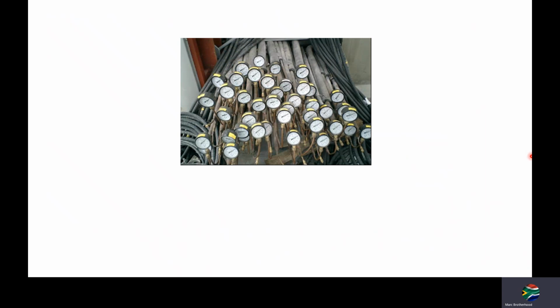If we look at this picture, multiple pressure gauges now at the end of the run of all the field pipework. And actually there's nothing wrong with this method. This is the correct method and the correct way to pressure test. At the end of pipework, you don't just go and stub quarter inch lines and pressure test halfway in the riser. This is the right way to pressure test.